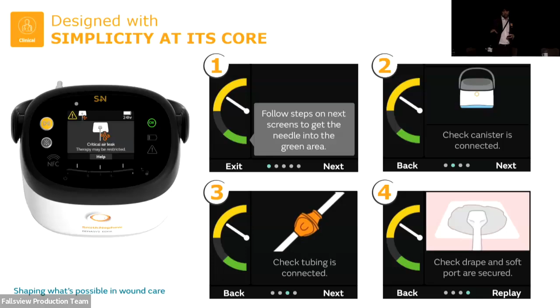Implementing something that we call self-test on the pump. It's simply a process that takes what, 30, 45, 40 seconds, 25, where basically the pump checks every single functionality, whether it's the different buttons externally or the pump internally. And after you do that, you basically have the pump ready and validated for the next patient.